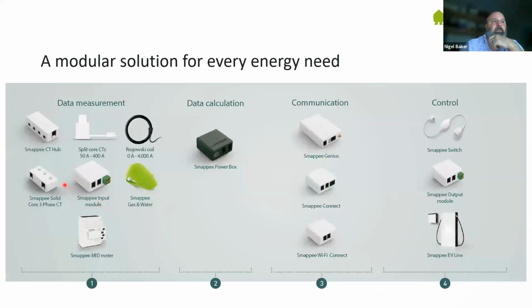So the split core CTs like this are actually class 0.5. The Rogowski coils are class 2, we don't get better in a Rogowski coil unfortunately. And the solid core CTs are class 0.2. The overall accuracy of our system is 1% or better, and the reason for that is this CT hub here, where you connect your CTs, that's a smart device with a correction factor built in. So I hope that answers the question.